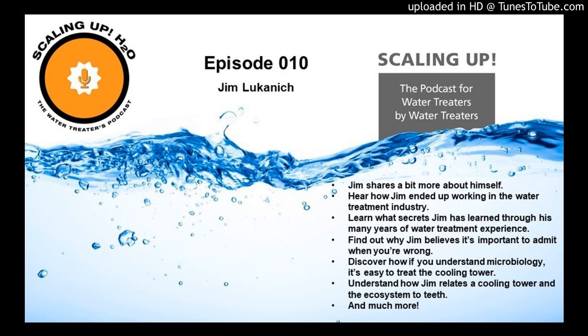But for today's show, we're just going to say that the closed loop is just as important as that cooling tower loop. And you know what that tower looks like when you don't feed biocide. Well, it's a lot easier to see. Of course, we've got a more dynamic system with the cooling tower and sunlight might be getting in. But we have things that are growing in the closed loop as well. So please give the closed loop the respect that it deserves and give your profession the respect that it deserves. If you are going to take care of a customer's systems, make sure that you're completely taking care of those customers' systems. Treat for all 4 areas of water treatment: scaling, corrosion, microbial fouling, and taking the dirt and debris out of the system.